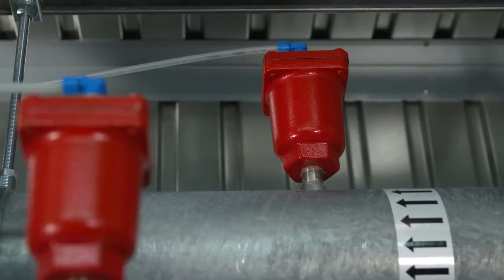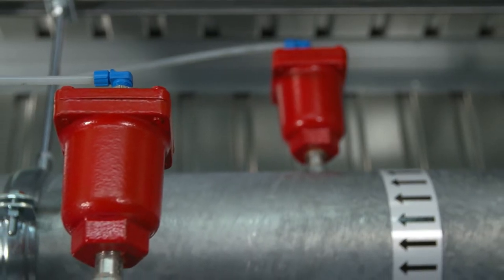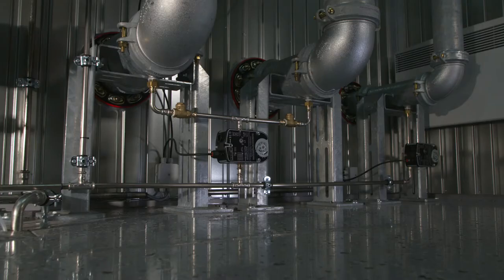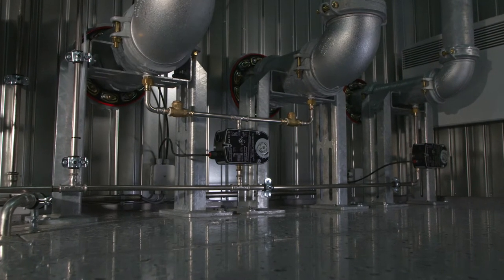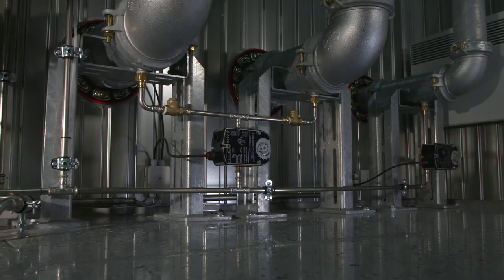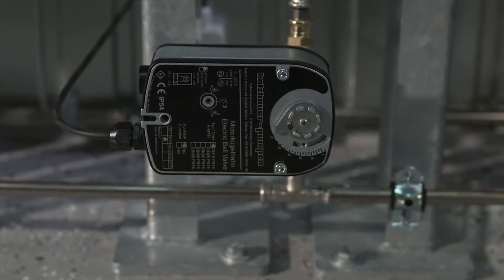All pipe fittings are equipped with air release valves; dripping water from air release valves is discharged through hoses into a common drainage connection. To prevent damage to outside pipes, the station is equipped with a fully automatic thermostatically controlled antifreeze drainage system, controlled by motorized ball valves and a common drainage pipe.